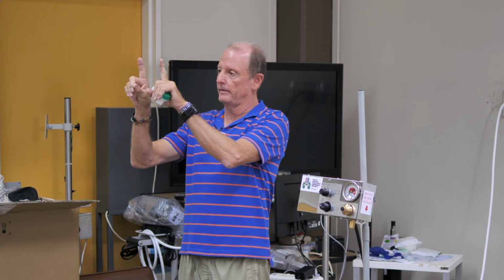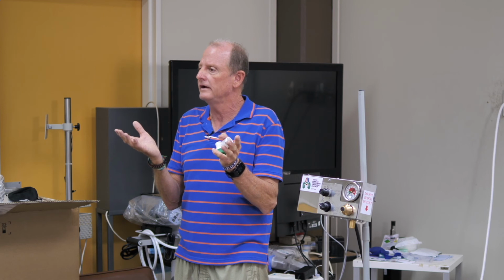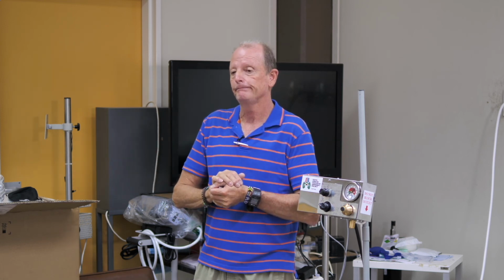Yeah. And there again with this, if you're running out of one, obviously you're going to get your alarms. But say, for example, you have the ideal situation where both your air and oxygen are going down. Your ventilators are going to stop, but this thing will carry on, as long as you don't have a big pressure differential, down to when you're at 280 kPa on both of them, and still get 60 litres a minute flow out of it. Yeah, that's the ideal situation. But you're never going to get that. Your air is going to be here and your oxygen is going to be there. It never drops. No, it will not drop. There are not enough points for it to drop. Yeah, correct. You haven't got the big draw out of the whole hospital.